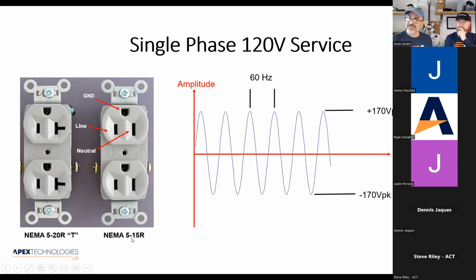In the world of NEMA, 5 means it's a 125 volt max. That means we use it for our 120 volt service, but it's a 125 volt max system. 15 is the current level, 15 amps. R means it's a receptacle.